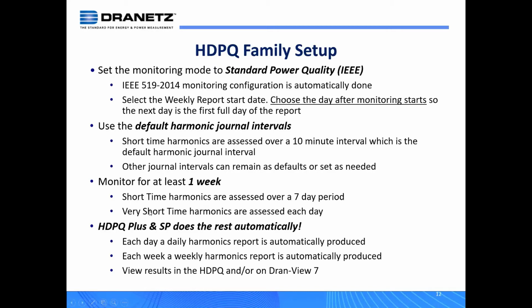The very short time harmonics are assessed each day. So in my example, if we start tomorrow, you'll get Thursday, Friday, Saturday, Sunday, and so forth. But those are also assessed over a weekly period as well. So the minimum reporting period or recording period should be 1 week.